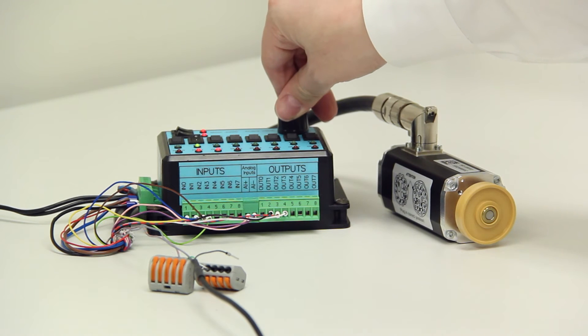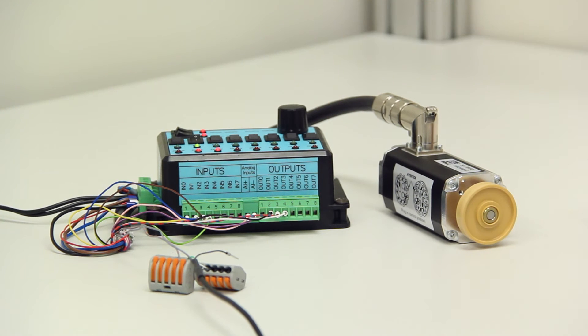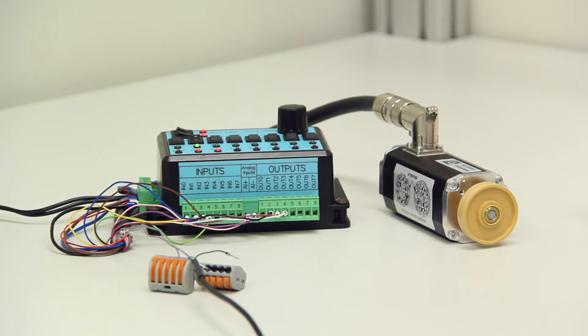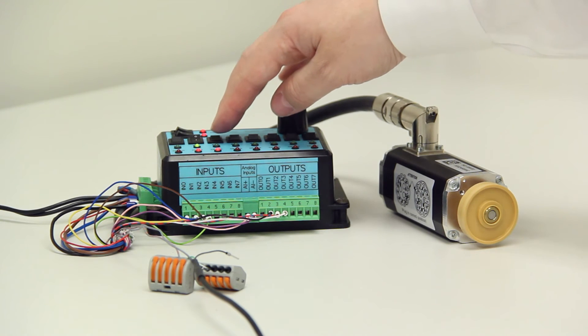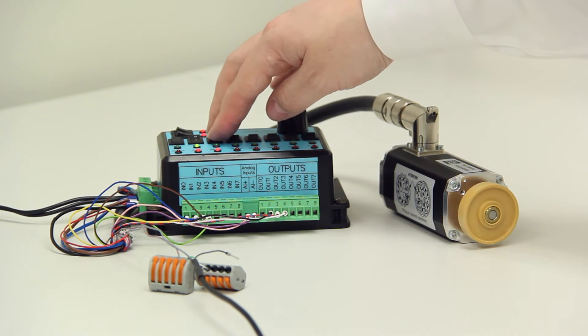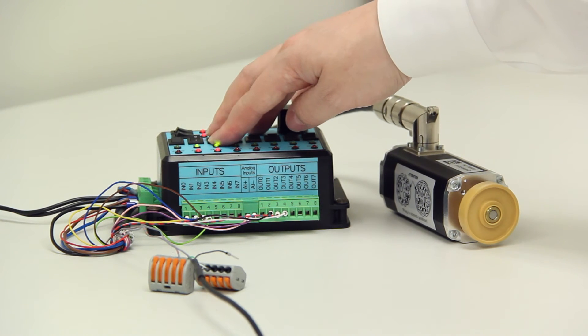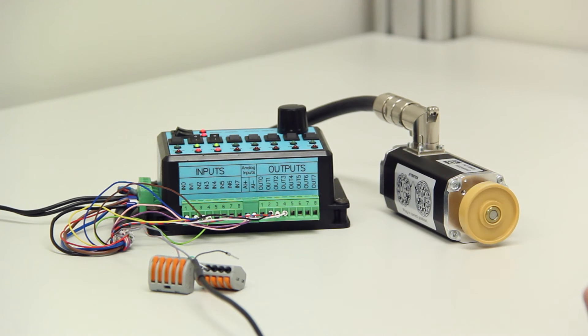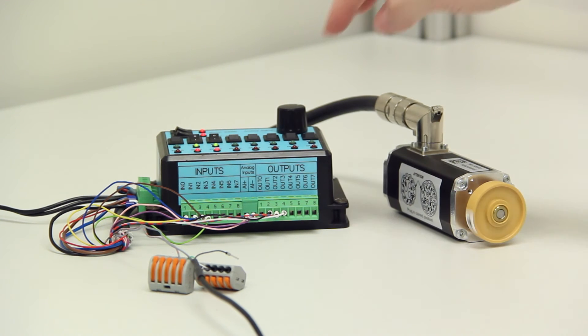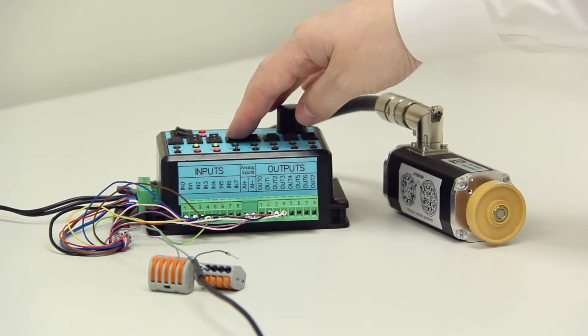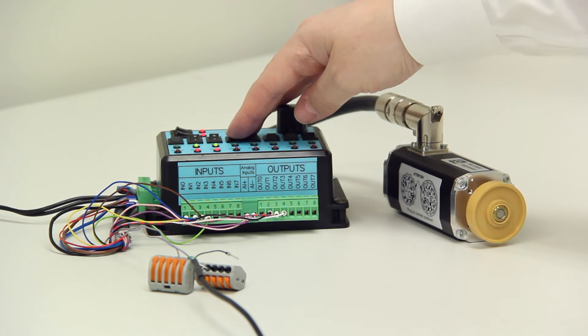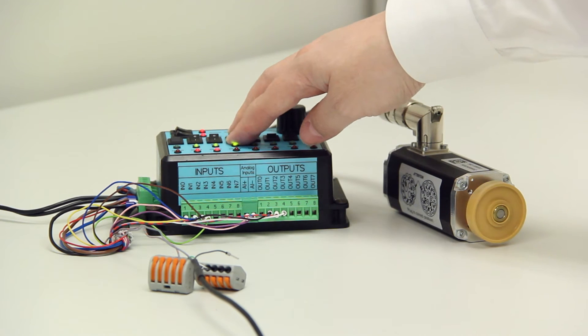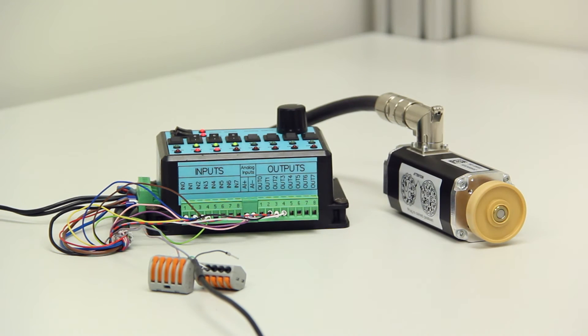The motor also comes with two fixed digital speeds, a low speed and a high speed. To select the low speed we select input 2. This selects the low speed operation. To select the high speed operation we turn on input 3 as well and that selects the high speed operation.